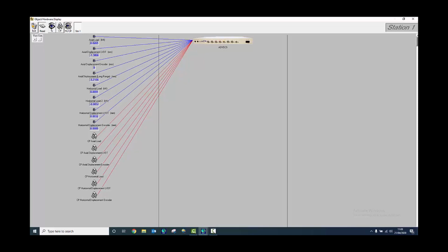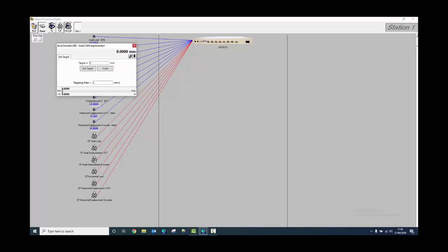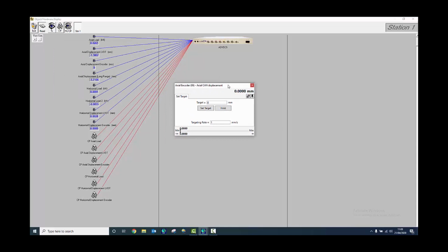And then looking at the control parameters, we have the control of the axial load, axial displacement LVDT, axial displacement encoder, which is the motor feedback, and then horizontal load, horizontal LVDT, and horizontal displacement motor control from the encoder. So open up the axial first and just make sure we can safely move it. So let's say move it down by 1 millimeter in the positive direction.